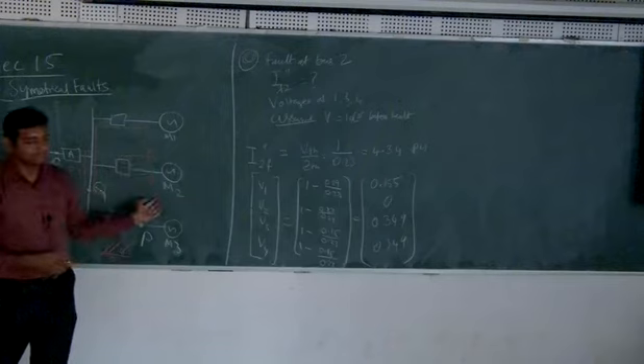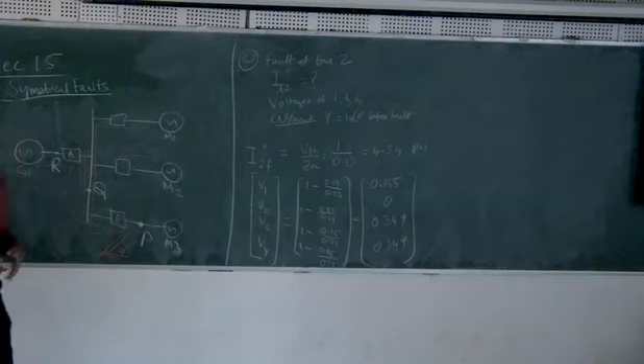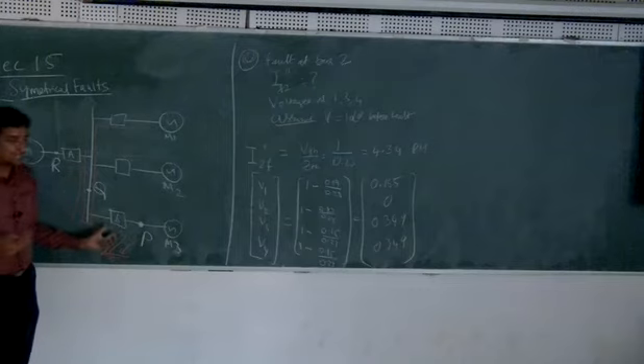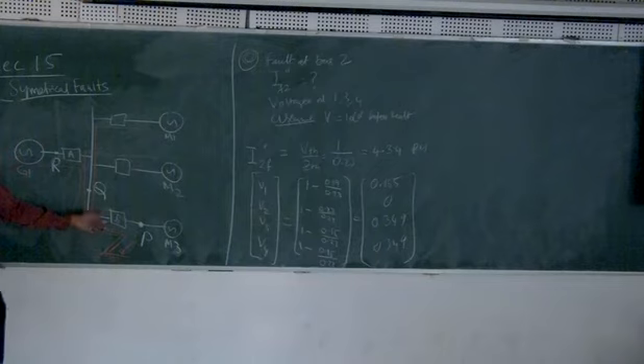So M1 and M2 are not interrupted. So you should design it accordingly. What if you design it in such a way that A itself opens? If A itself opens, then all the three machines will be disconnected. So depending on the fault current, if there is a heavy fault current, then that should operate first. There should be some kind of coordination in designing this. That's just a point.